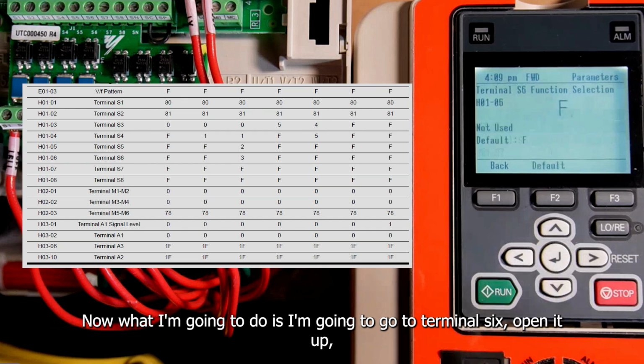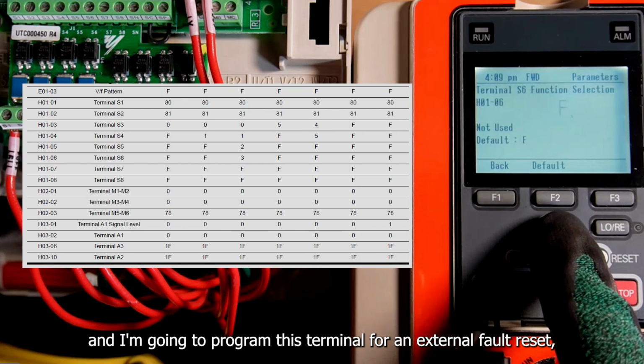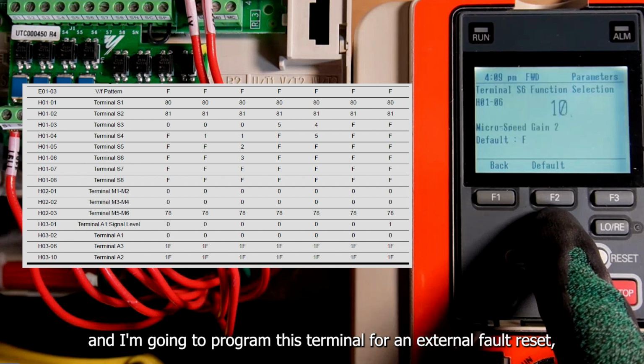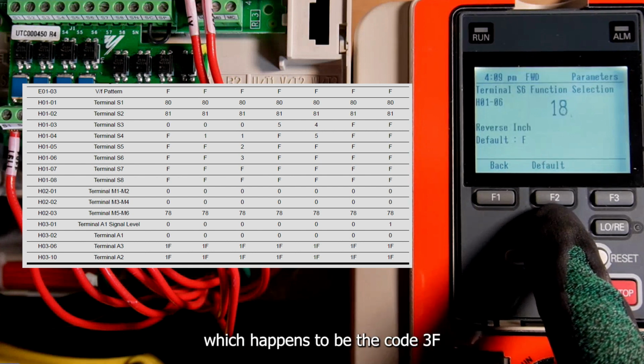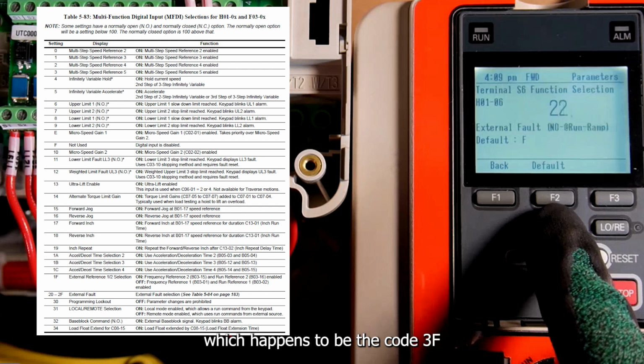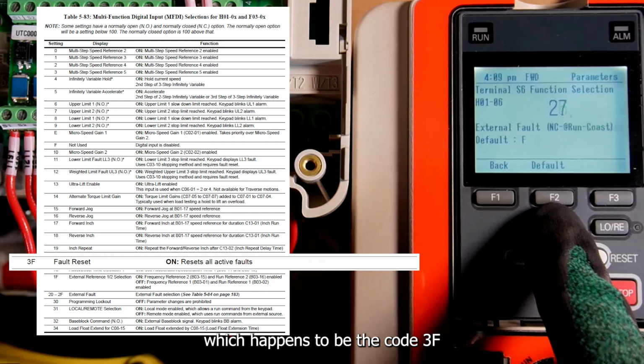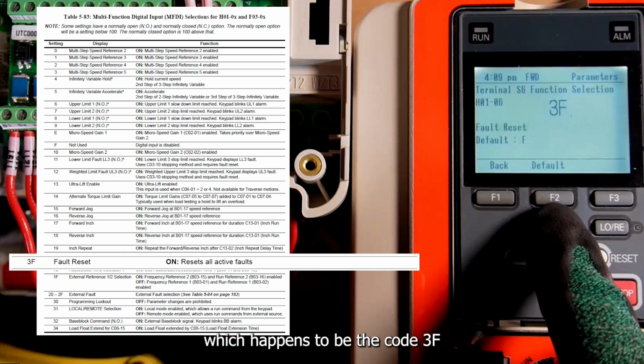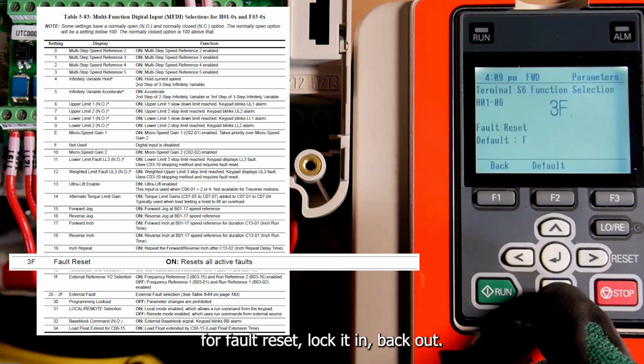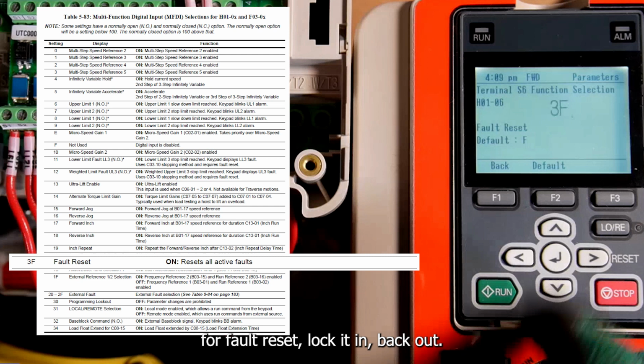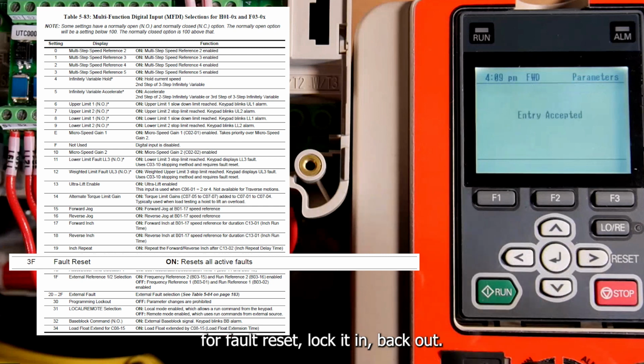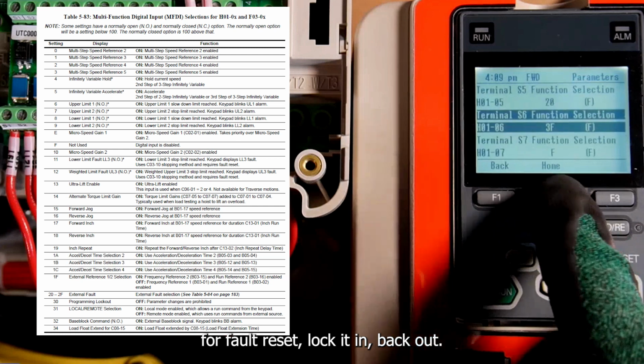I'm going to open it up, and I'm going to program this terminal for an external fault reset, which happens to be the code 3F. Fault reset. Lock it in. Back out.